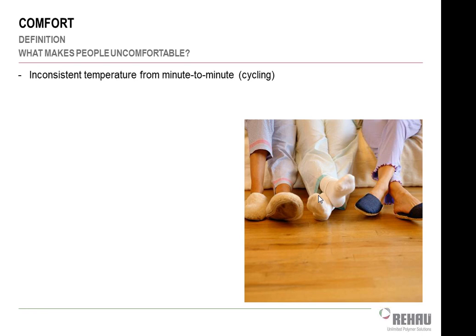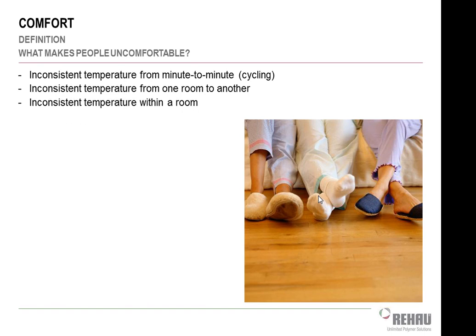And even though the boiler may modulate, the floor temperature in the space is not going to fluctuate at all. It's going to be within tenths of a degree all day long. So it's very consistent temperature and comfort. The temperatures from room to room are also very consistent. Radiant heating is based on the floor shining on you, as we're going to talk about here in a minute, not so much the air temperature. But we're able to keep one room to the other very consistent. And within the room, it's very consistent as well.